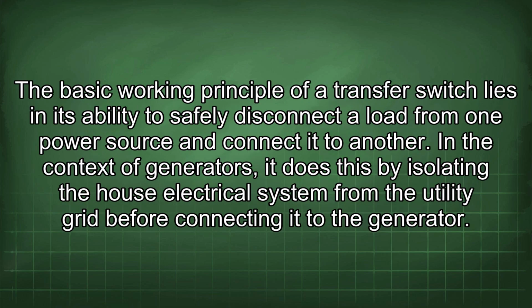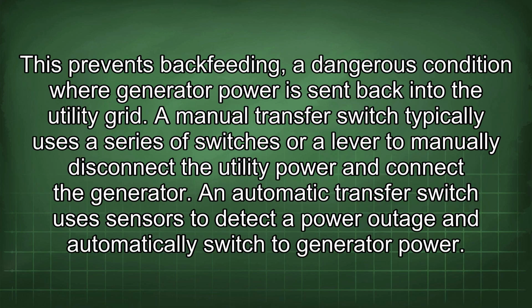The basic working principle of a transfer switch lies in its ability to safely disconnect a load from one power source and connect it to another. In the context of generators, it does this by isolating the house electrical system from the utility grid before connecting it to the generator. This prevents backfeeding, a dangerous condition where generator power is sent back into the utility grid.